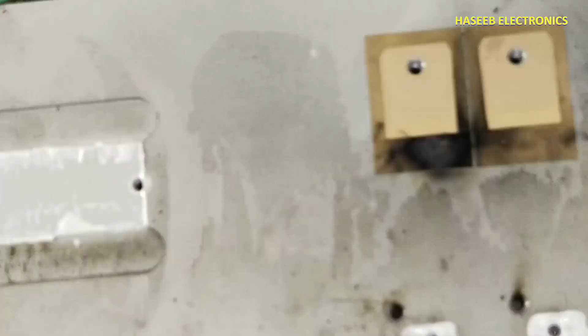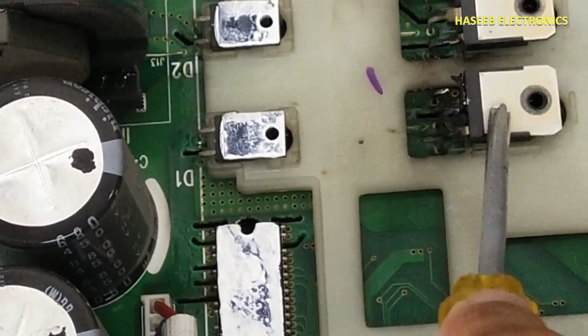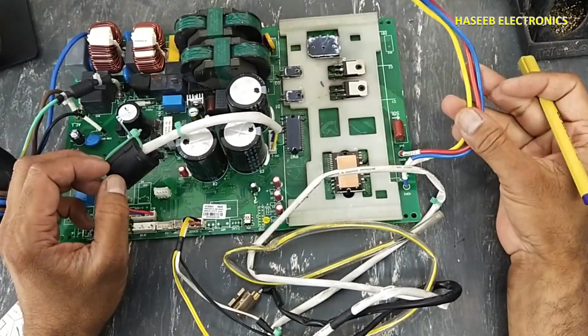We can see it was reported with a communication fault. But we can see the fault condition: this IGBT is damaged. Now we have this board. It has this output connector. One output connector is here. Input 4 wires here: one is the earthing wire, chassis ground, neutral, line, communication. Here are the sensors, overload protector, 4-way valve.